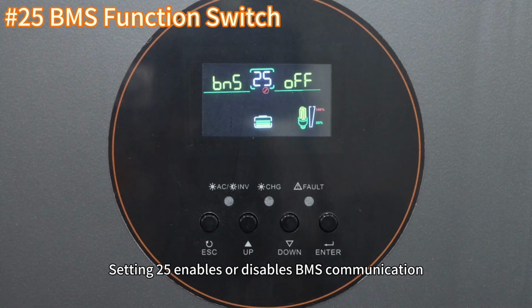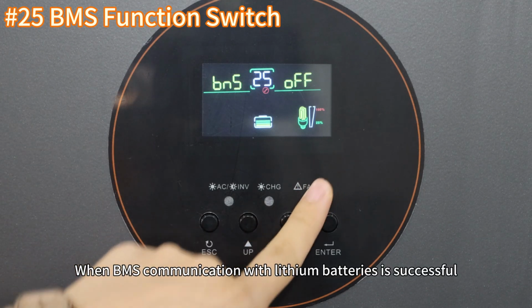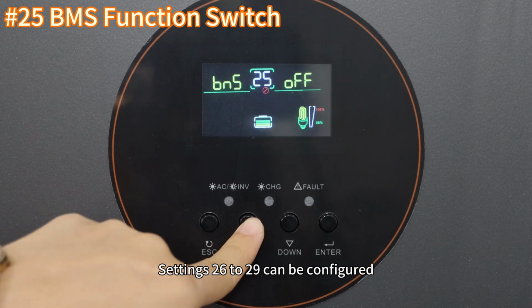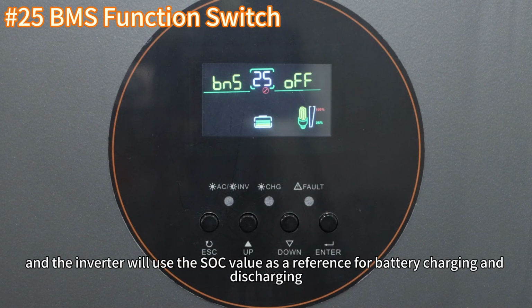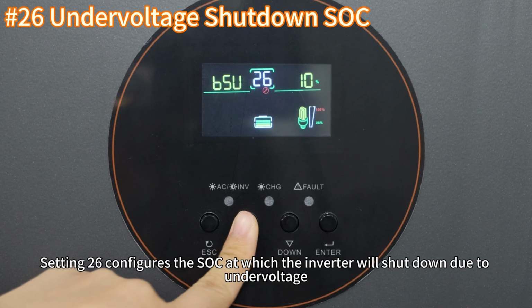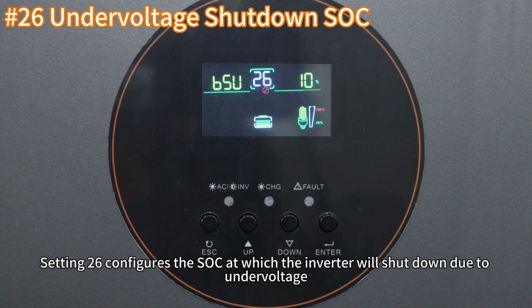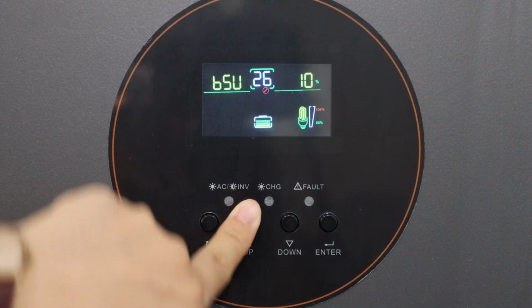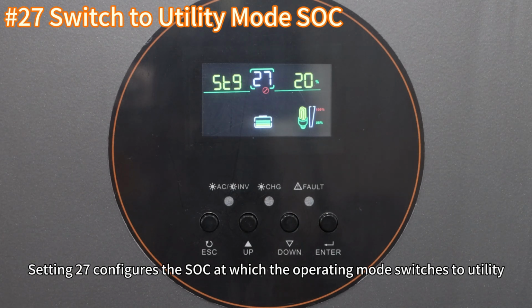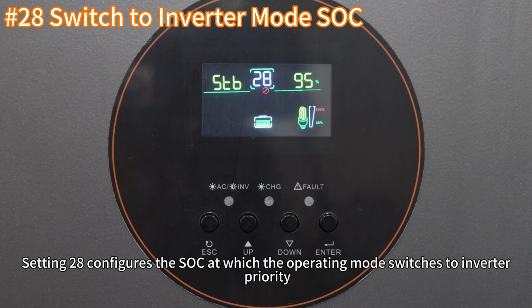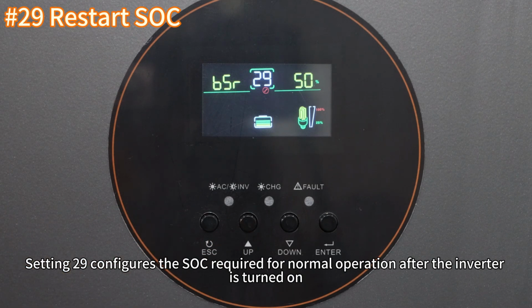Setting 25 enables or disables BMS communication. When BMS communication with lithium batteries is successful, settings 26 to 29 can be configured, and the inverter will use the SOC value as a reference for battery charging and discharging. Setting 26 configures the SOC at which the inverter will shut down due to undervoltage. Setting 27 configures the SOC at which the operating mode switches to utility. Setting 28 configures the SOC at which the operating mode switches to inverter priority. Setting 29 configures the SOC required for normal operation after the inverter is turned on.